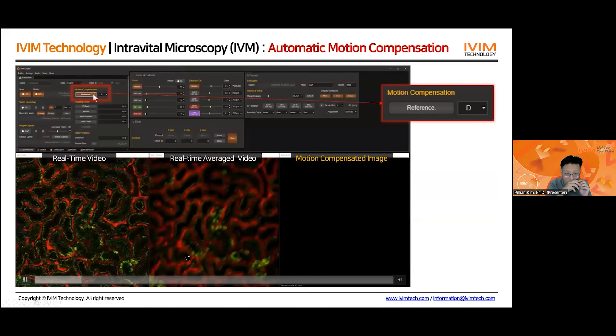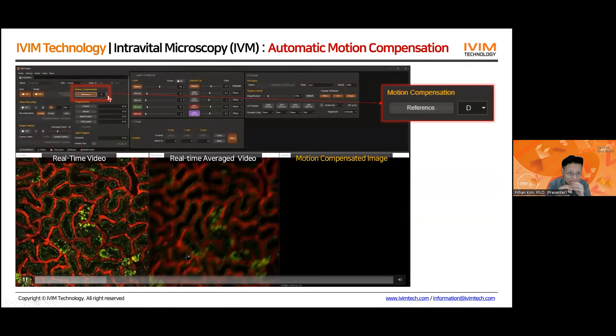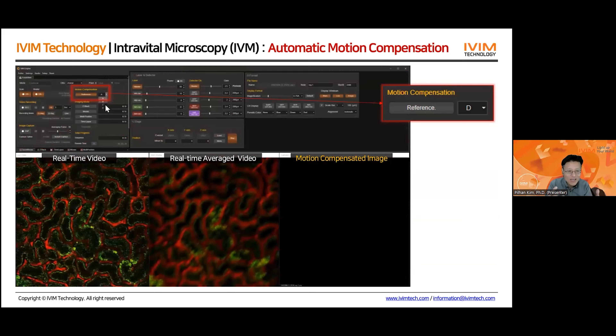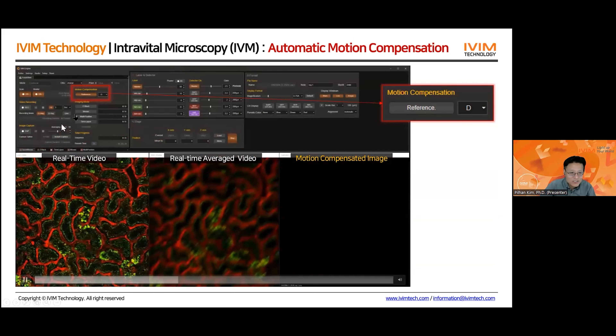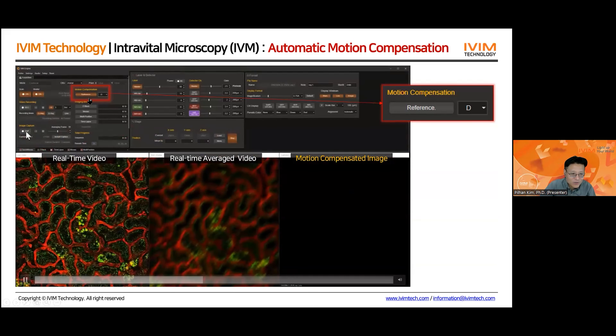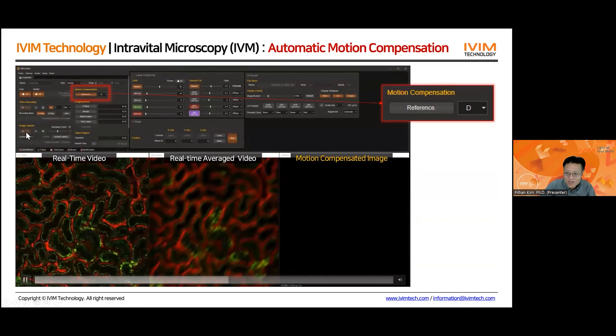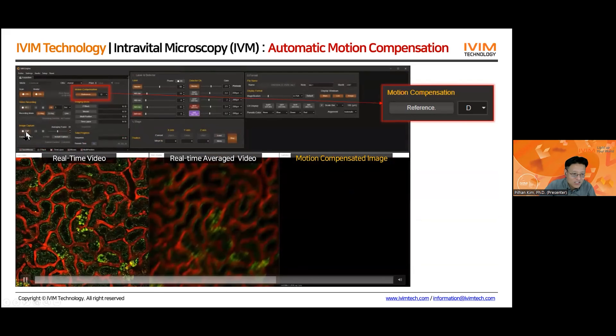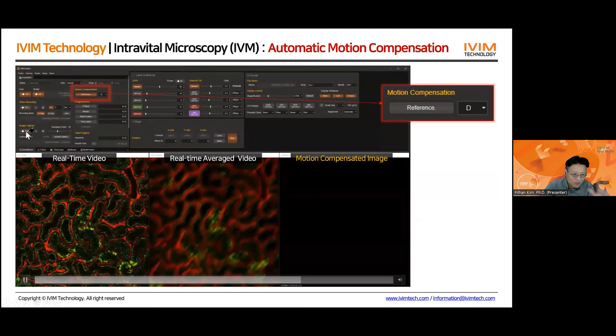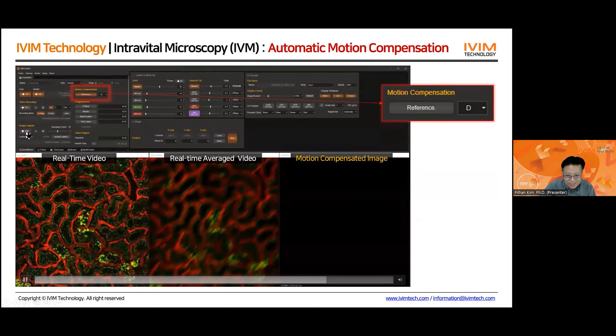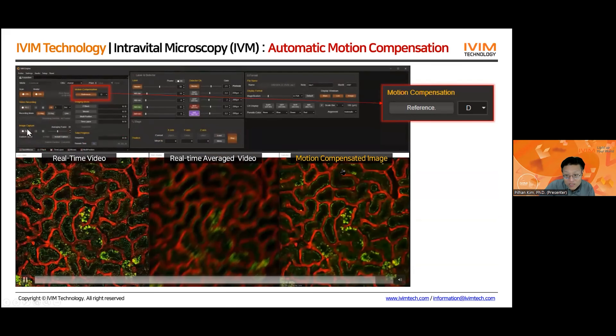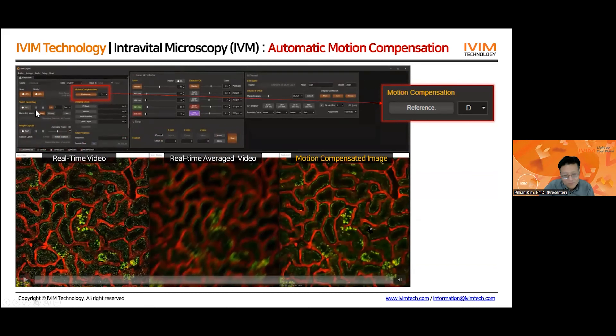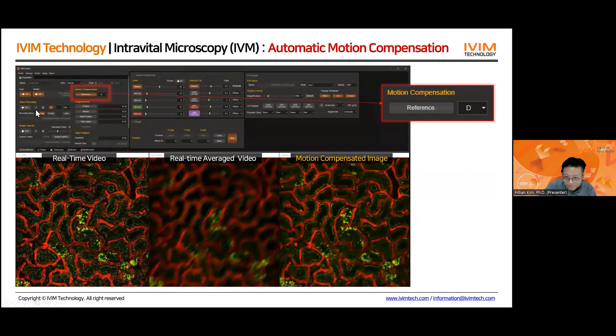You can compare with and without motion compensation from these video-rate videos. The live tissue shows very typical movement under the microscope lens — we definitely need this motion compensation function to get very high, sub-micrometer resolution from live tissue. Our software automates this motion compensation — just activate the function and click a single button to get the motion-compensated image out of the real-time video.